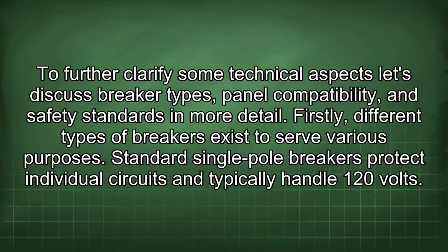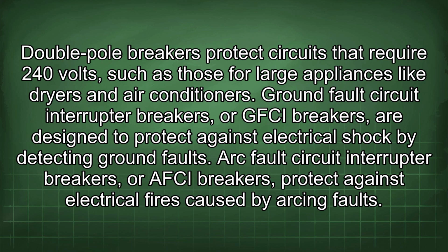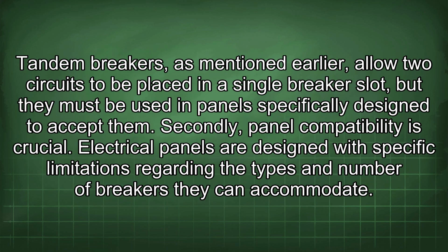Firstly, different types of breakers exist to serve various purposes. Standard single-pole breakers protect individual circuits and typically handle 120 volts. Double-pole breakers protect circuits that require 240 volts, such as those for large appliances like dryers and air conditioners. Ground fault circuit interrupter breakers, or GFCI breakers, are designed to protect against electrical shock by detecting ground faults. Arc fault circuit interrupter breakers, or AFCI breakers, protect against electrical fires caused by arcing faults. Tandem breakers, as mentioned earlier, allow two circuits to be placed in a single breaker slot, but they must be used in panels specifically designed to accept them.